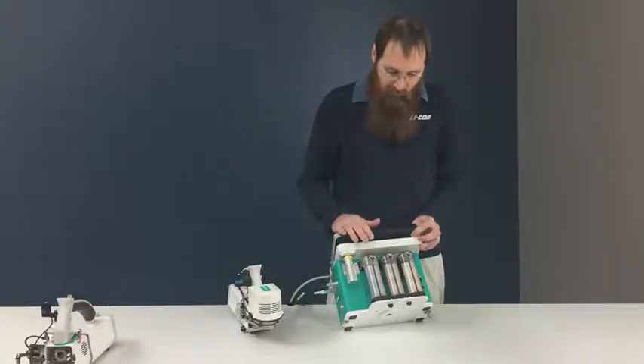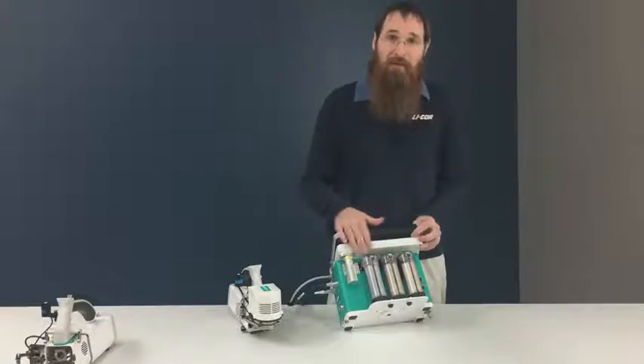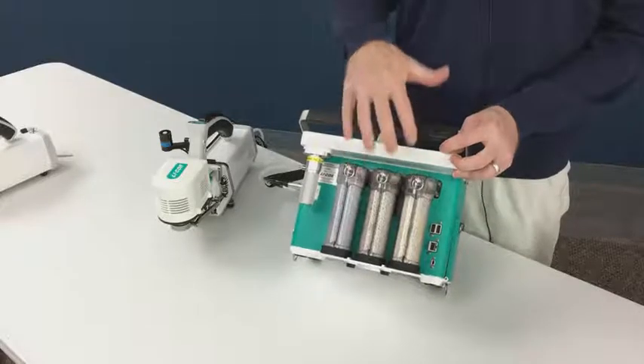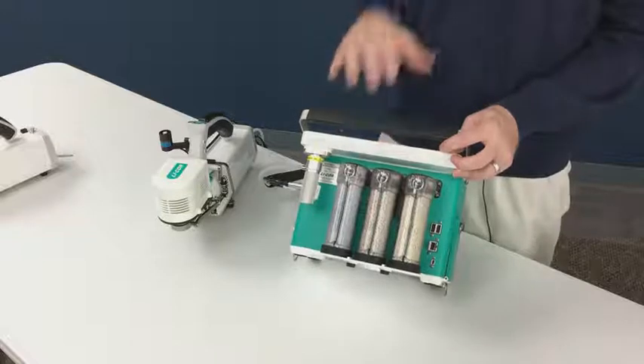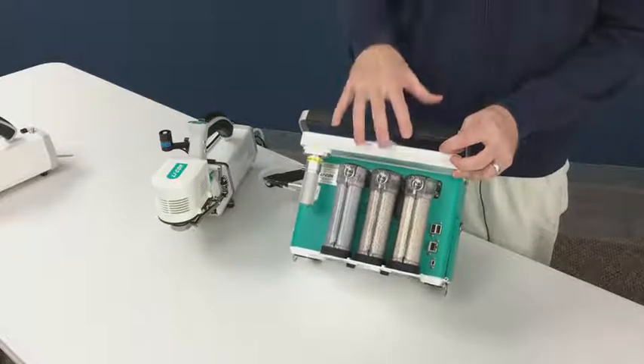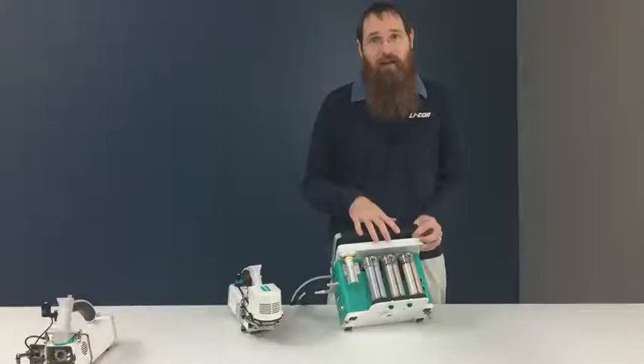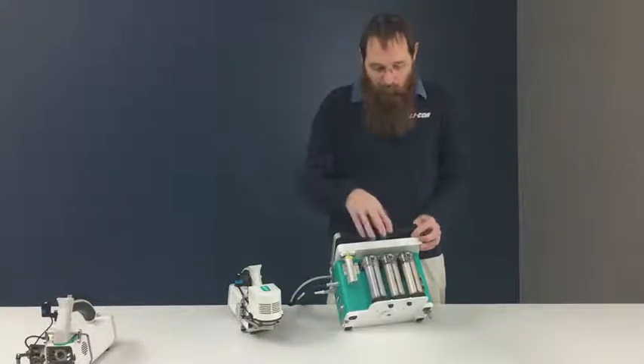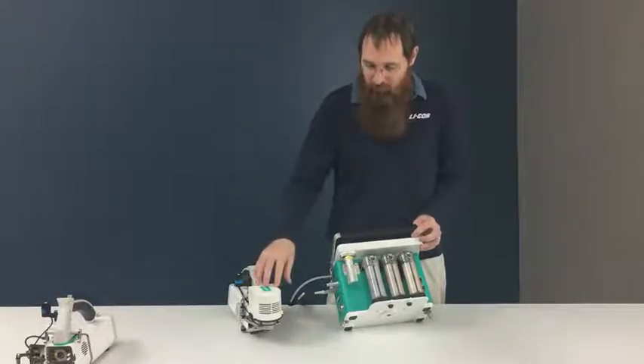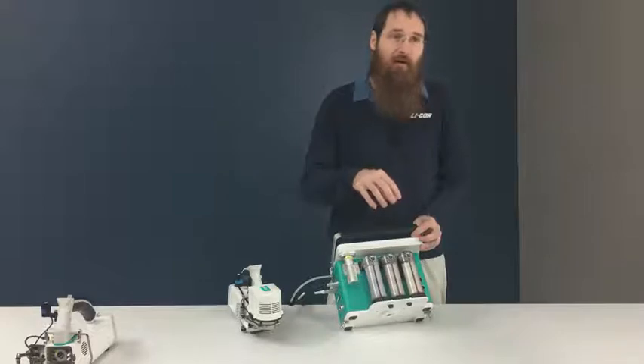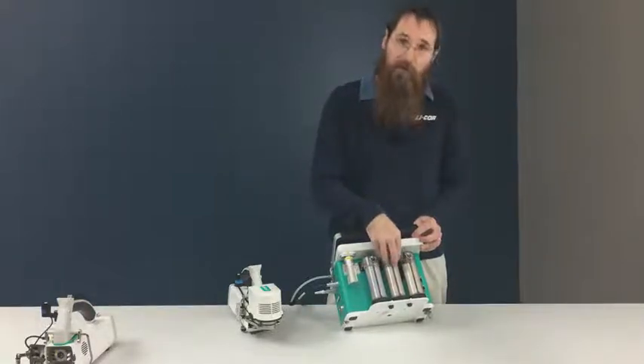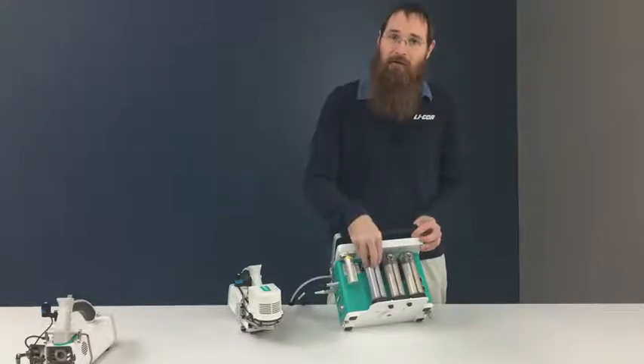On our 6800 here, there are no knobs, right? Flow to these chemical columns is all set with valves inside the console that are under computer control. And that means to do things like water vapor control in our chamber, the instrument can automatically, for us, proportion the airstream between adding water to it and taking water out of it, which is pretty cool.